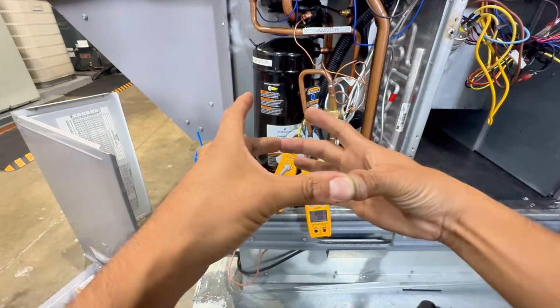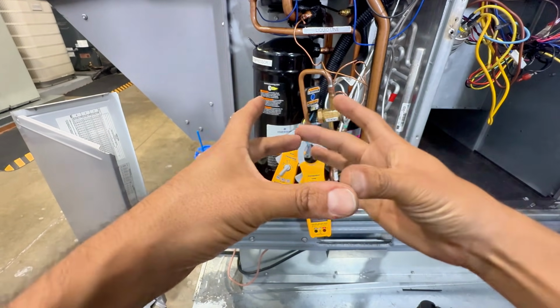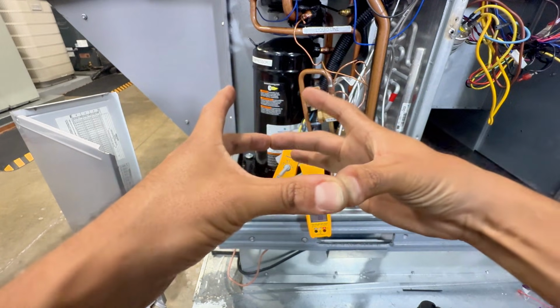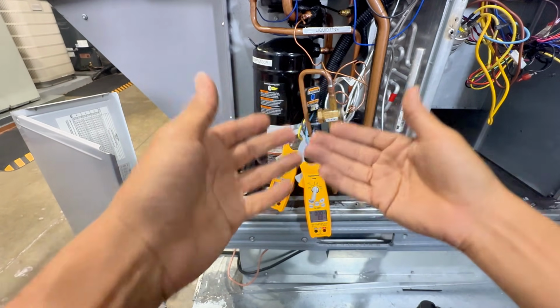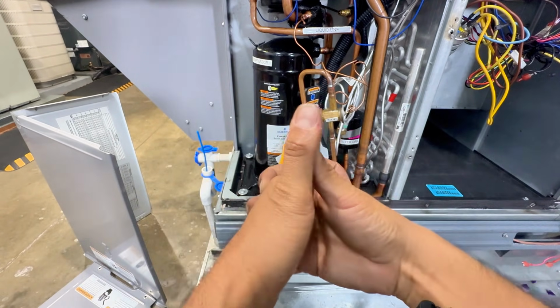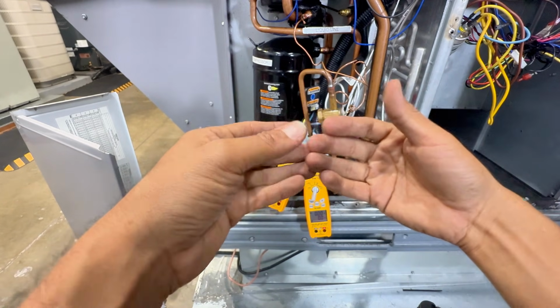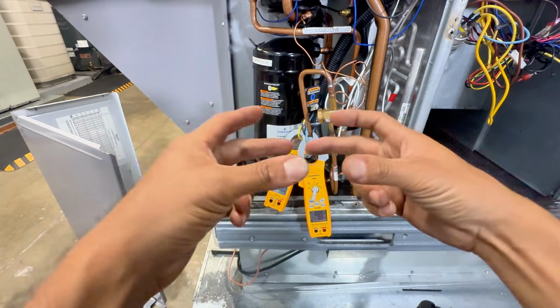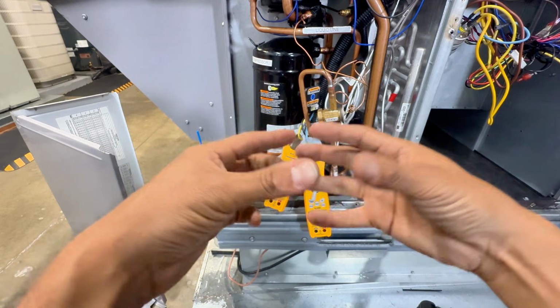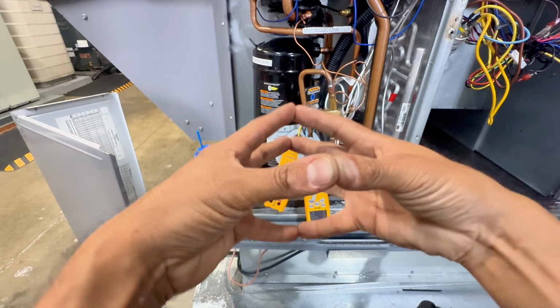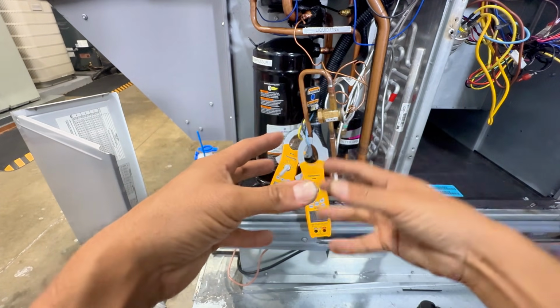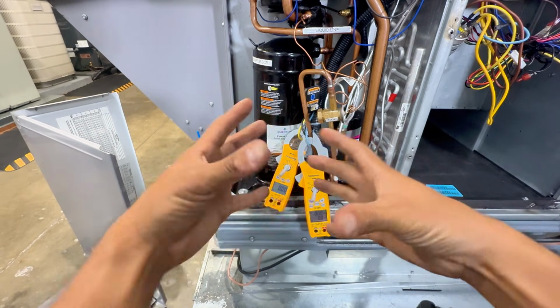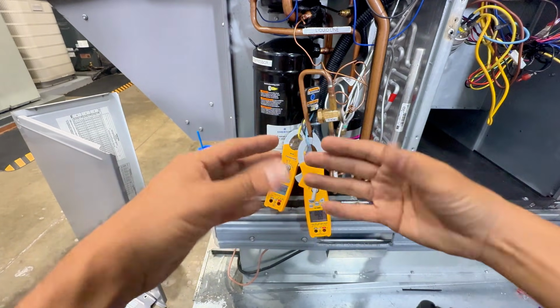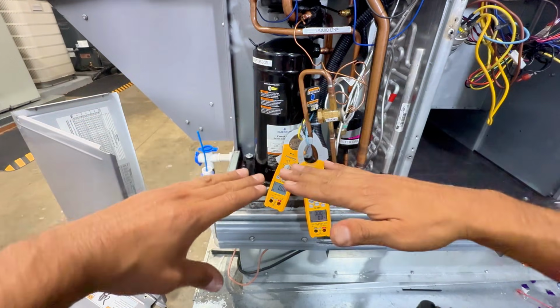The compressor is locked. It can't move because there's no capacitor. It's pulling all that amp and it doesn't know what to do with it. So instead of becoming an inductance, a load, now it just becomes a resistive heater. It basically becomes a heater. The heat just stays there.